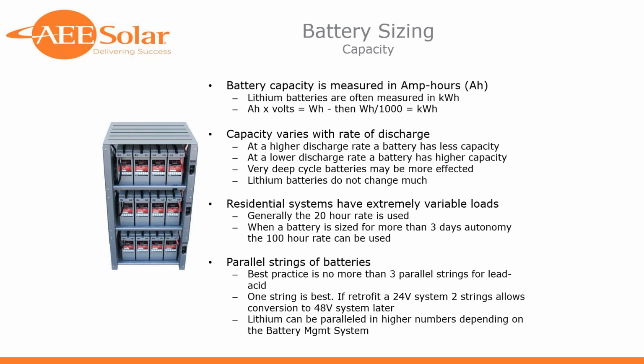And also, at least in lead type batteries, the capacity varies with the rate of discharge. You can discharge a battery in 1 hour, but that total capacity is going to be considerably less than if you discharge it in 10 hours, which is considerably less than if you discharge it over a period of 100 hours. So you have to get an idea of what rate you're going to be discharging that battery, and use that capacity of the battery, not some different lower or higher capacity. Lithium batteries tend to be able to push out the power at high rates or low rates, and they're much less affected by the rate of discharge as far as their total capacity.